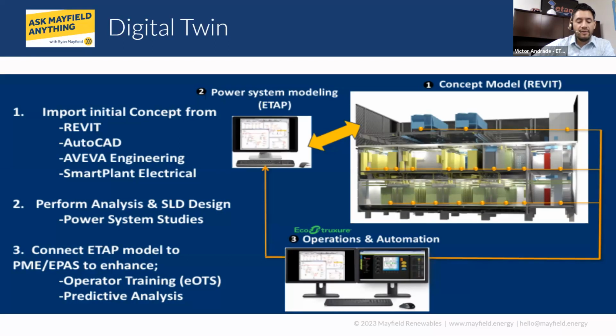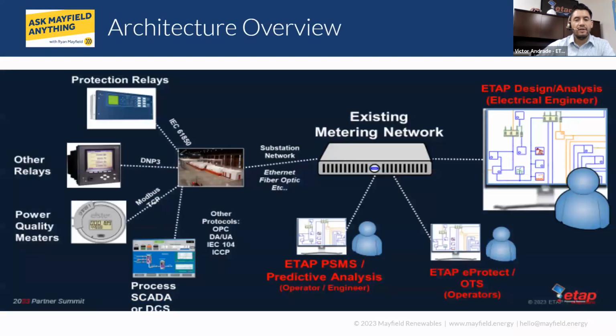A lot of engineering firms start with a conceptual design that is in Revit. A lot of times it's three-dimensional, for example. ETAP does have a bi-directional interface with Revit, with AutoCAD, Aveva Engineering, SmartPlant Electrical, as you could see on the screen. And then the digital twin is when ETAP is connected to a power monitoring or SCADA system, right? Operations. And the real value to that, next slide, is on the connectivity to an existing network.